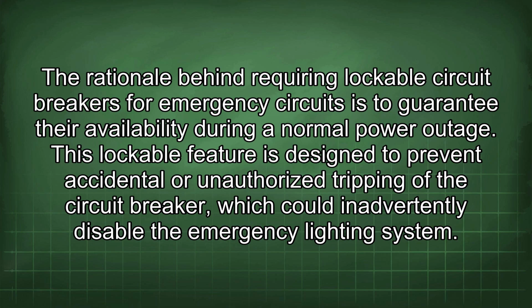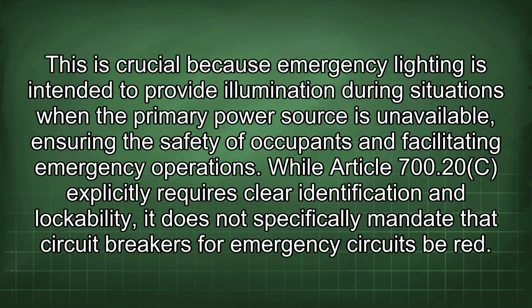This lockable feature is designed to prevent accidental or unauthorized tripping of the circuit breaker, which could inadvertently disable the emergency lighting system. This is crucial because emergency lighting is intended to provide illumination during situations when the primary power source is unavailable, ensuring the safety of occupants and facilitating emergency operations.